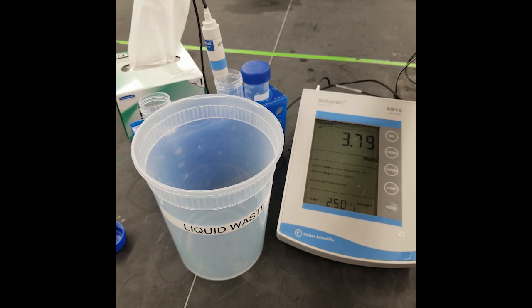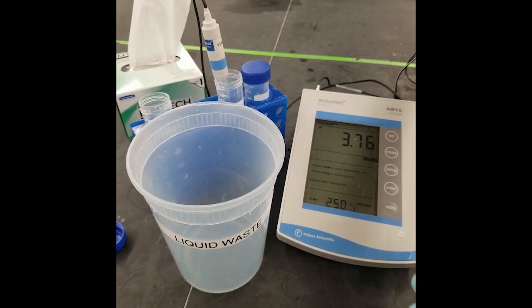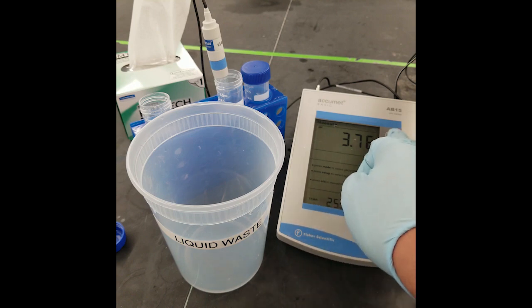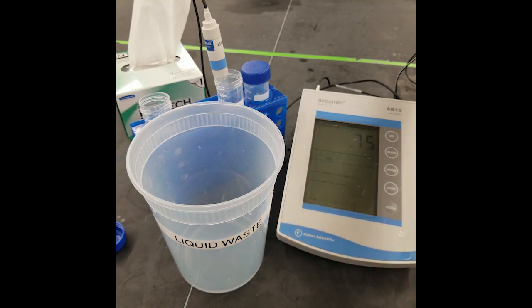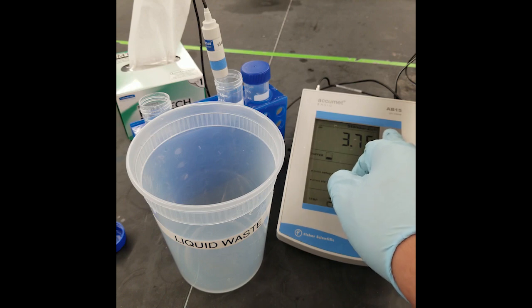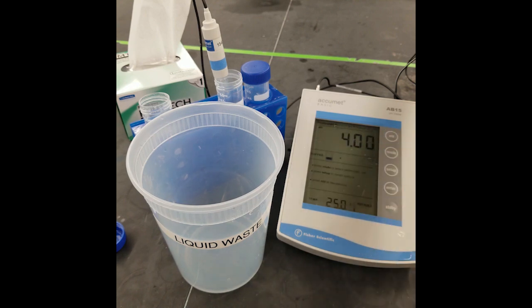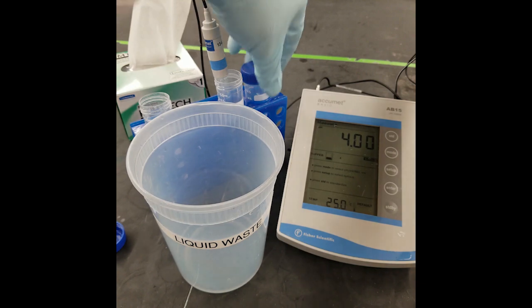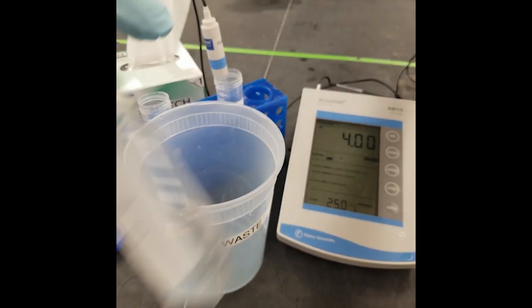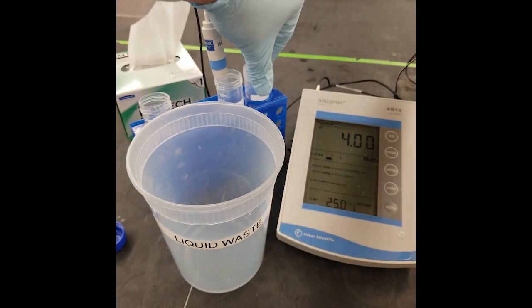You'll see that it rapidly changed to a pH close to 4. Right now it's stabilizing at about 3.77 or 3.79. And then after about 10 seconds of it stabilizing, you're going to want to hit the standard button once. That is going to enter you into the standardization mode. And then hitting it one more time is going to program the electrometer to recognize that solution as having a pH of 4, since that was the closest reference point it was at. And then we're just going to repeat the whole thing using the pH 7 standard solution.